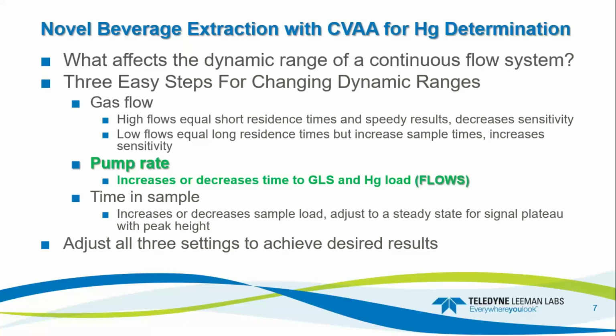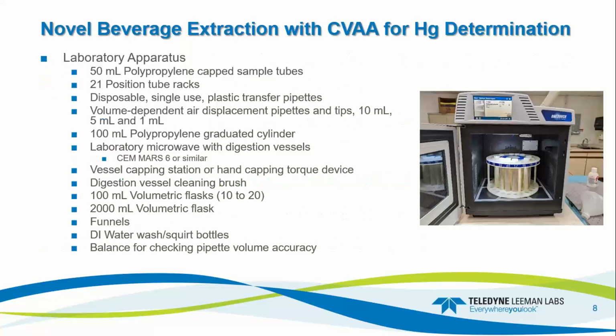Pump rates, you can increase or decrease the pump flow or the liquid flow to the GLS, that's your mercury load, and then time in sample. This is going to be the time that the probe is pulling the sample out of the sample tube and sending it off to the instrument for ultimate detection. So you adjust all three of those, or one or two of them, and you can achieve the desired dynamic range and results that you would like for your methodology.